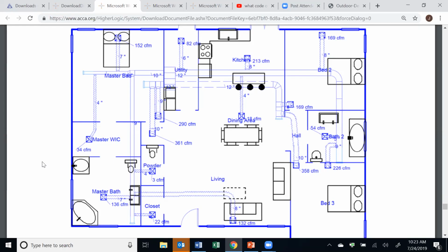Again, if necessary, have that conversation with the contractor and understand that he had to relocate the trunk because of this web truss, or a system that went upstairs that he didn't know about when the plans were handed to him, or maybe some framing detail. HVAC contractors, electricians and plumbers, we're all fighting for similar real estate, and sometimes they get there before we do.